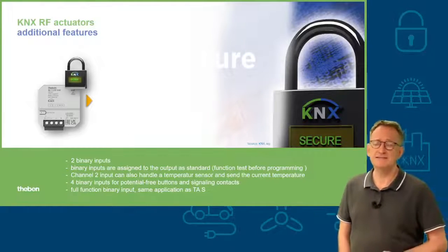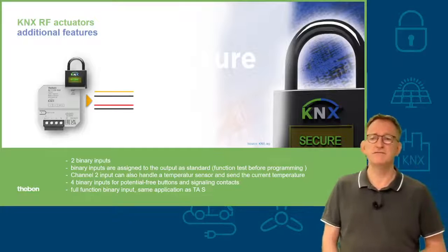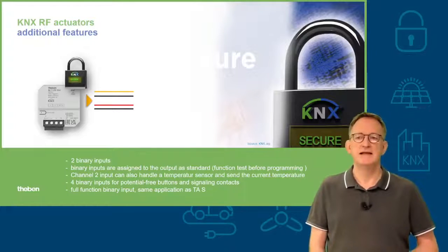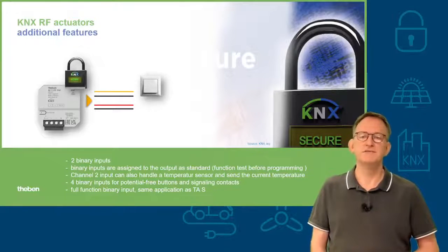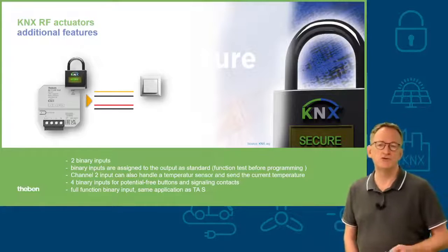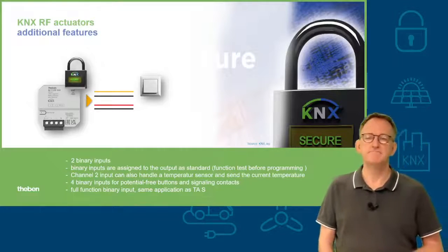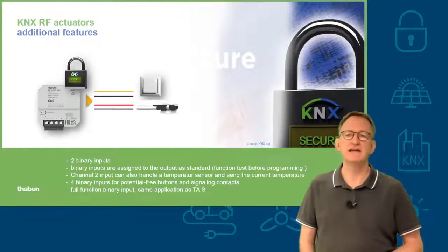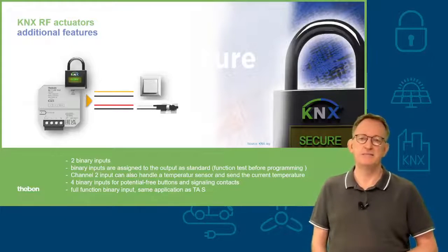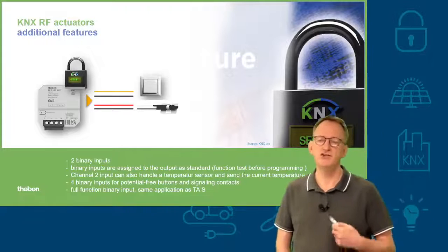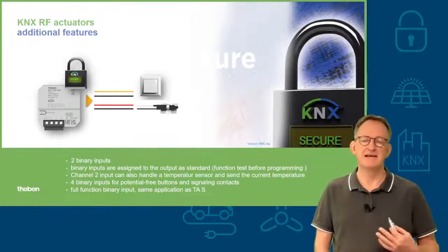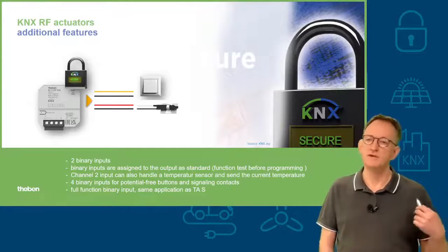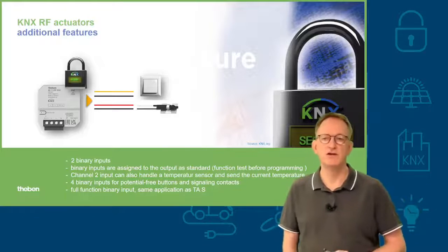Each device has some inputs. They have 2 binary inputs except for the TU4, which has 4 inputs. These devices can be used for various purposes. Either you can just connect a normal push button to it, independent of which vendor you prefer, but you can also additionally add a temperature sensor to channel 2. So each device can also act as a classic temperature sensor and send the temperature of a room to the bus, which can then also be used for heating regulation.